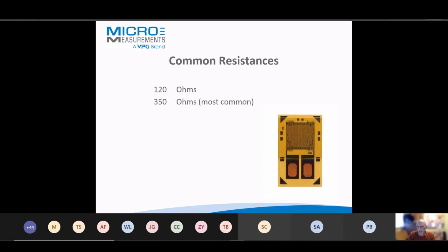But 350 ohms is the most common if you're doing general stress analysis or building a load cell. Most commercial load cells will be 350 ohms. We're using more 1000 ohm strain gauges because of battery power, preserving battery life better. And we're doing more 5000 ohm gauges, which are becoming easier to manufacture with our advanced sensor technology.